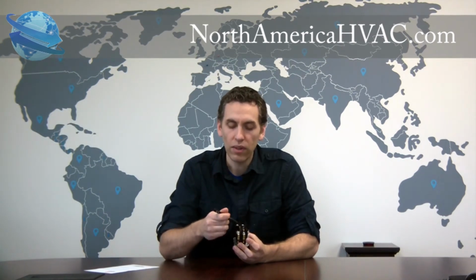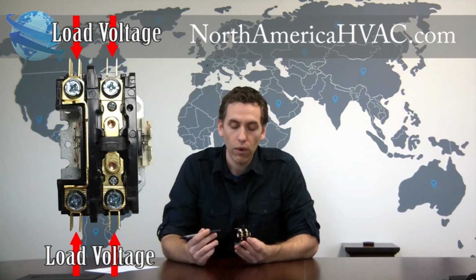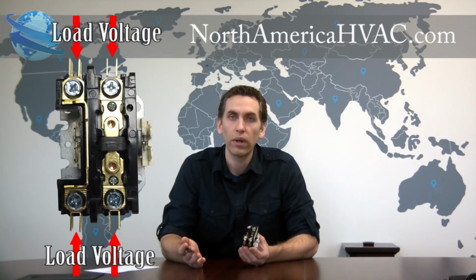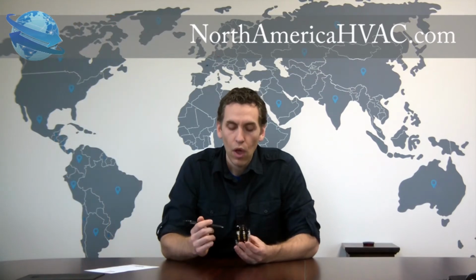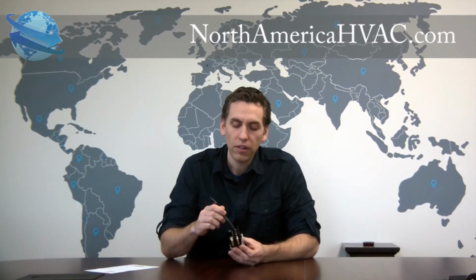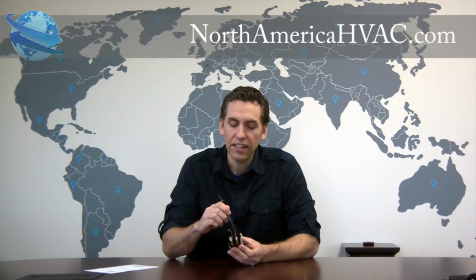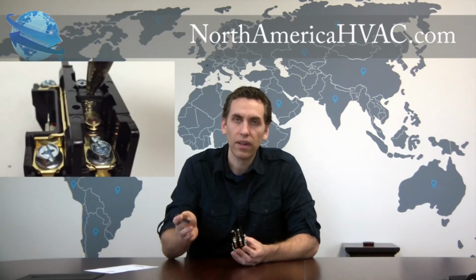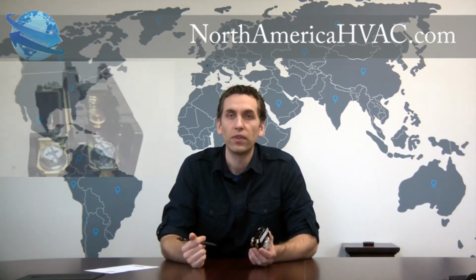The voltage that you're applying to the top of the relay is known as the load voltage, and the load voltage can be a variety of different voltages: 24 volt, 110 volt, 220 volt. You can change that up. The real question is, how do we get this button to push down and make the connection between the bottom and the top of our contactor relay? And that's where the coil voltage comes in.